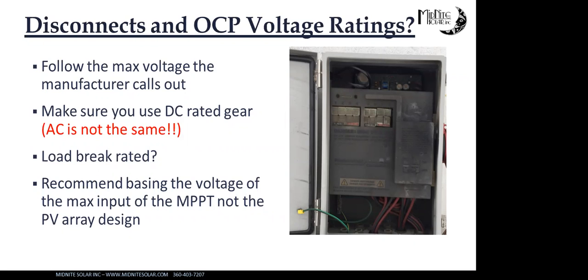And the other one is just finding out what the voltage of the equipment is. This particular combiner box we're looking at here that you can see caught on fire, those fuse holders in the front of it say they're 1,000-volt DC. But the box, and it is clearly labeled on the box and marketed as such, is only good for 600 volts because of the DC switch. The installer saw the 1,000 volts on the fuse holders and didn't look at the label on the side of it, and when the switch opened, it caught on fire.